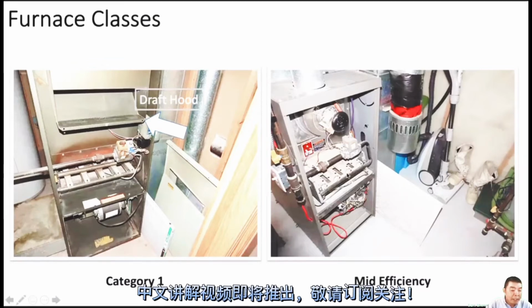Mid efficiency furnace. So like this one. Normally we know there's an inducer motor like this one. So category 1, the low efficiency, there's no inducer motor. As for the mid efficiency furnace, there is a subclass of its own, more efficient than category 1. Because there's an inducer motor, it can help to keep more efficiency in the house.